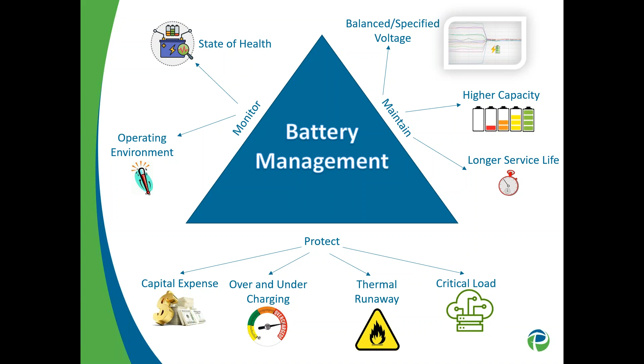When we talk about design life and service life, it's a common question that gets put out there, and they kind of get mixed together. When somebody asks what's the design life of your battery, people typically say that a standard 12-volt VRLA would be 5 years - but that's actually the service life. If you look deeper at the battery data sheet, you'll see a design life of 10 years for a typical VRLA product, or 20 years for vented lead acid. There's also some VRLA product that is 20 years design life - it's just based on the design.